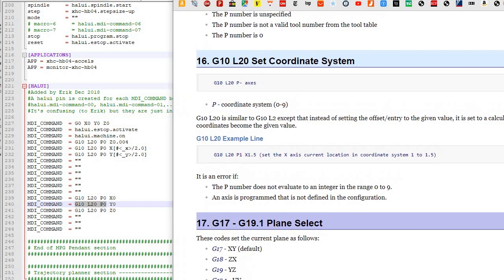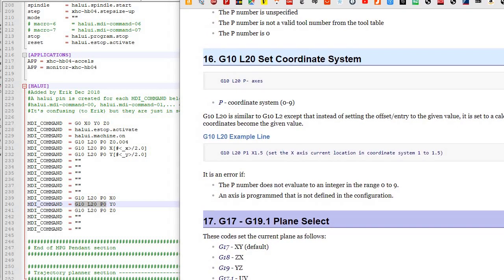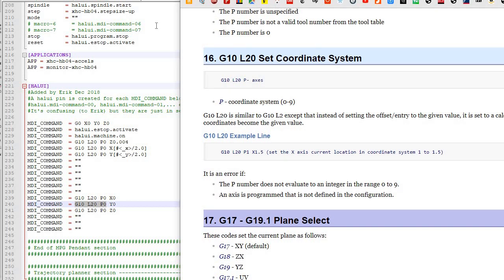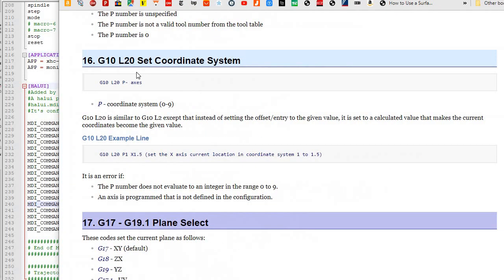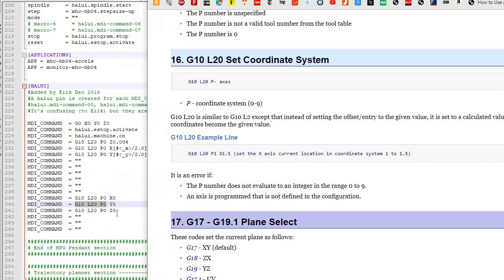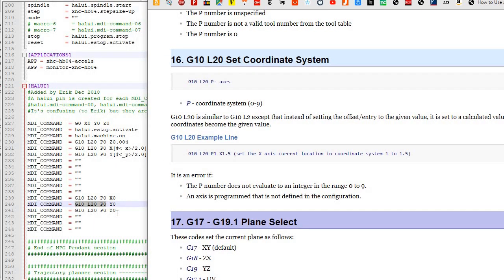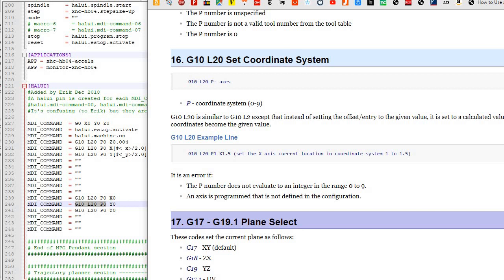This is the LinuxCNC gcode reference. So this is G10L20, a set coordinate system. So I'm going to set coordinate system P0. So set coordinate system 0. And I'm going to set y to 0, right? You could set it to some number if you want. So when I push that button, it sets coordinate system 0 to 0. So essentially zeros out the axis. And that's exactly what you want if you want 0 to be where your probe is, right? So let's go back.